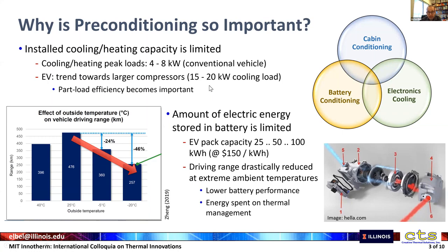What that also means is that as we're going to these larger and larger capacities, operation in so-called part-load efficiency becomes very important. This is why electric vehicle manufacturers mostly consider this type of scroll compressor you see here on the bottom, which is a machine that can be nicely speed controlled over a wide range without losing efficiency too much.